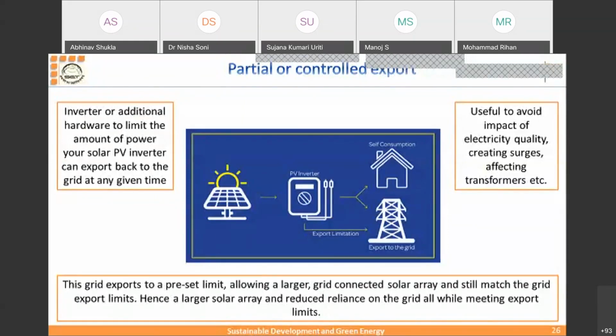Why do they look at it like this? Because they don't want imbalance in the grid, any kind of phase imbalance, harmonics more than 4%, or DC injection from the solar plant. There are certain power quality considerations, so they restrict solar power plants up to a certain level.